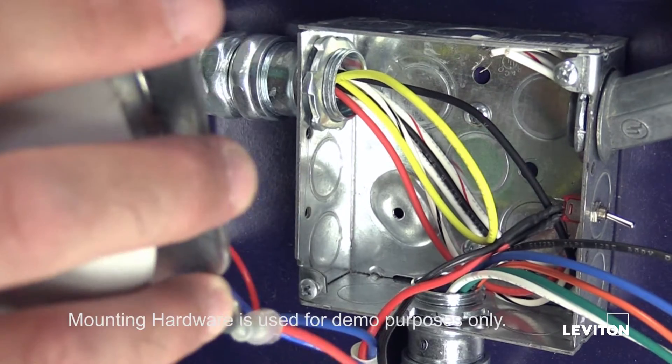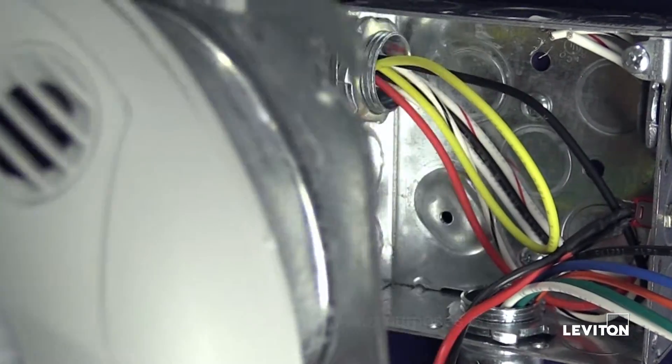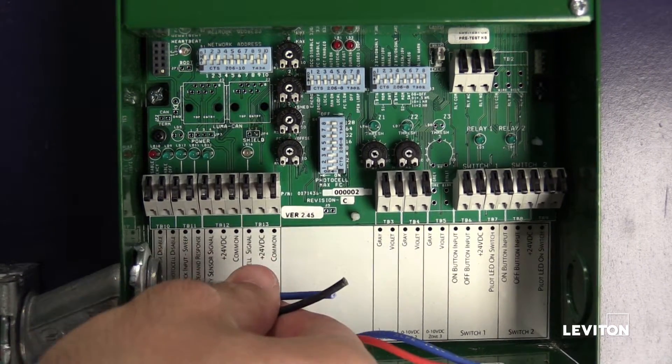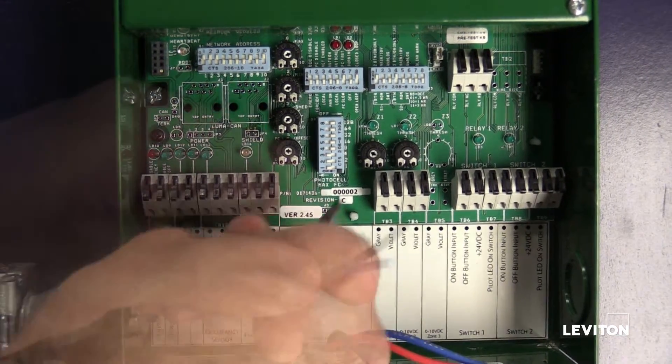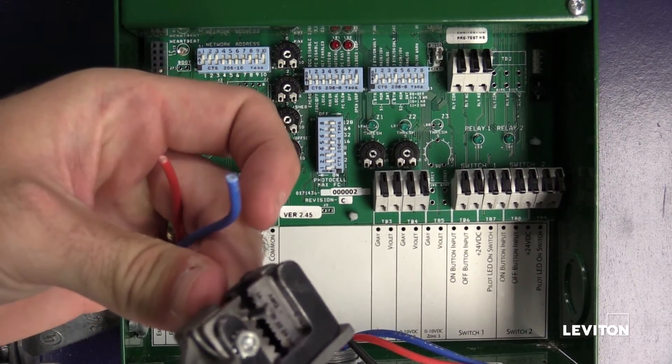Always be sure to verify and record the wire colors before landing the wire in your integrated room controller. Run your 18 gauge wire or CAT6 cable through the conduit connector feeding the IRC. Strip the ends of your wire to 3 eighths of an inch.